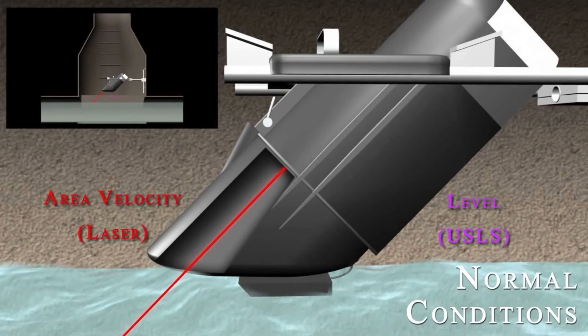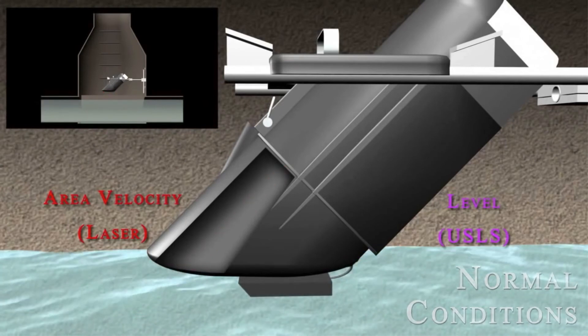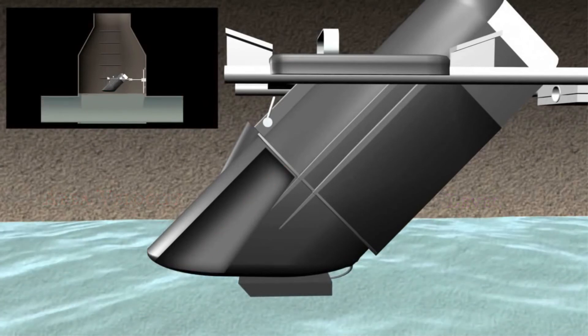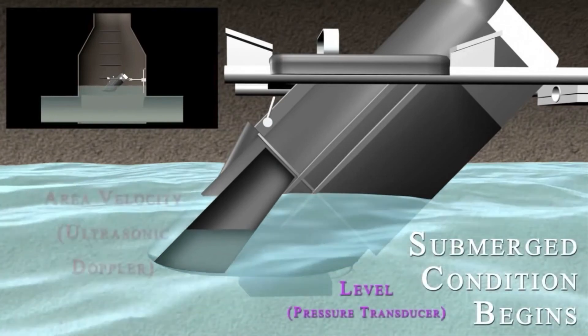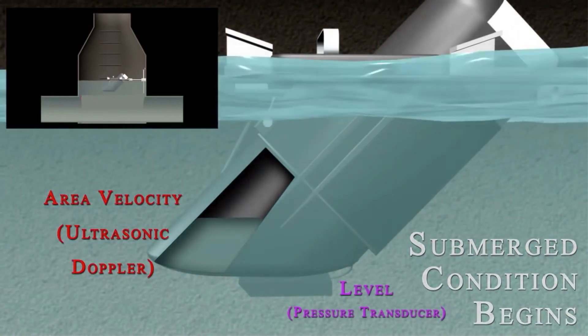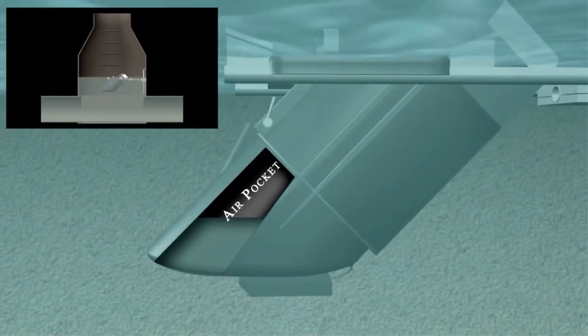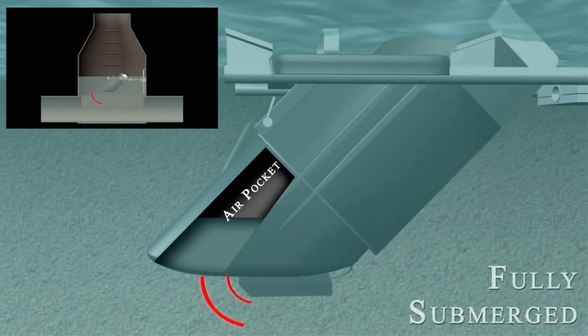During submerged conditions, flow measurement continues without interruption, with optional continuous wave Doppler ultrasonic area velocity technology. The sensor provides ultrasonic Doppler velocity measurement and differential pressure level measurement. The ultrasonic Doppler technology provides more accurate flow measurement during submerged conditions.